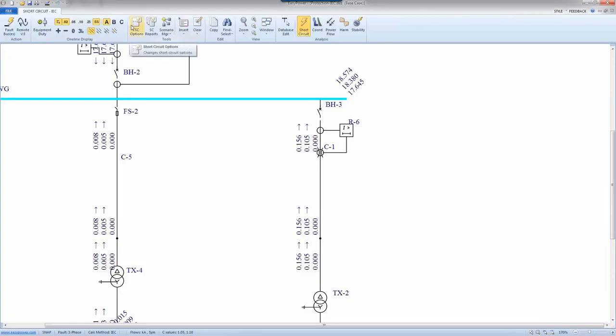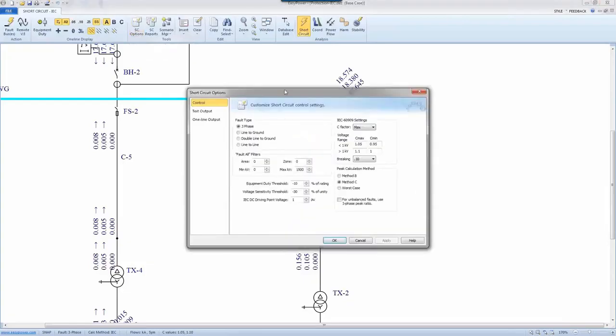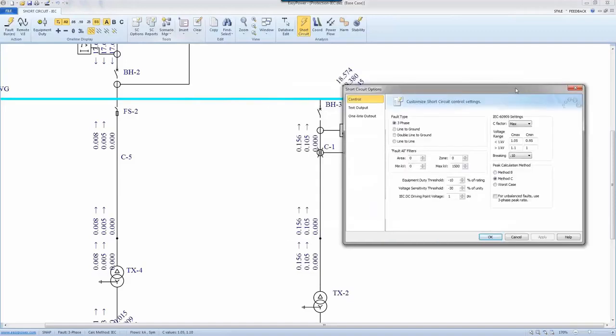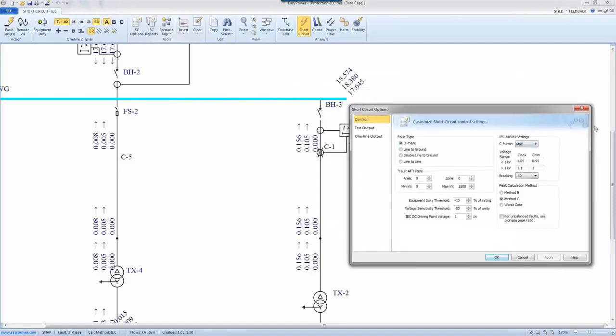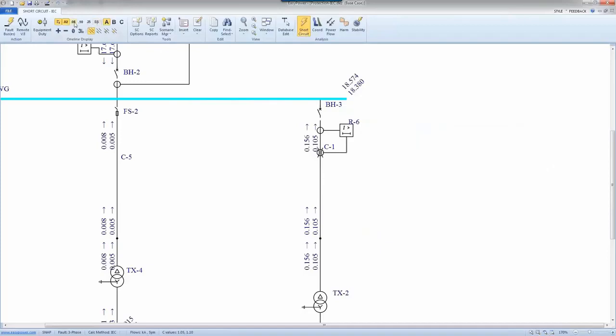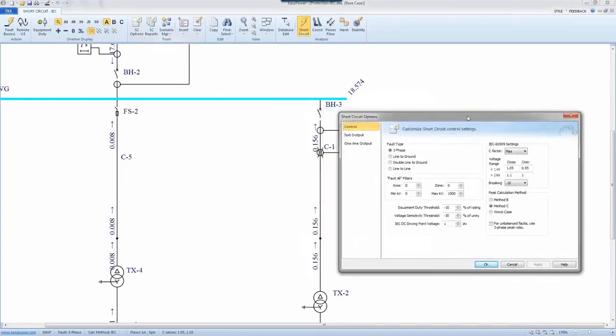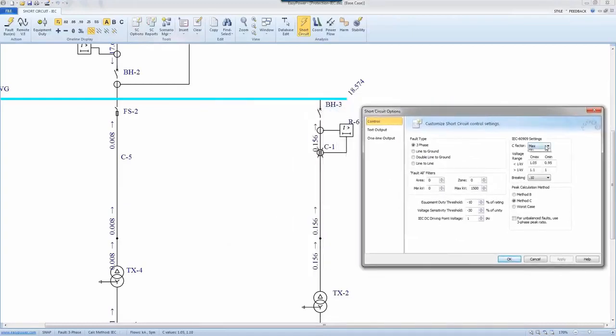Let me just go back quickly and talk a little bit about Cmax and Cmin. So this is Cmax, and if I go and change this value, let me just do that only for initial so that we can focus on one number. So 18. So Cmax, as I said, is a mechanism, leverage, parameter IEC defines and allows the user to play with so that it can come up with the range of the worst case scenario or the highest fault value versus Cmin for lowest fault value.